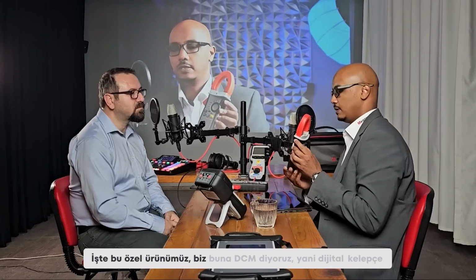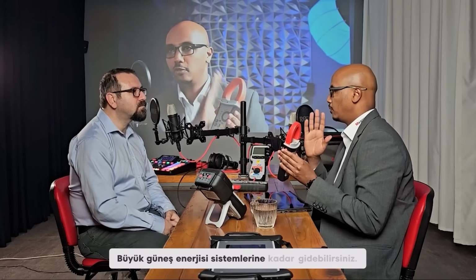So this particular product, we call it a DCM, a digital clamp multimeter. With the clamp side here, you can measure current, AC current or DC current. And this particular model can do up to 2,000 amps, so you can go all the way up to large solar systems. And from the other side, you can measure the voltage, up to 2,000 volts, ready to go. So a device like this is for measuring open circuit voltage, short circuit current, operational voltage, operational current. These are tests that should be done.